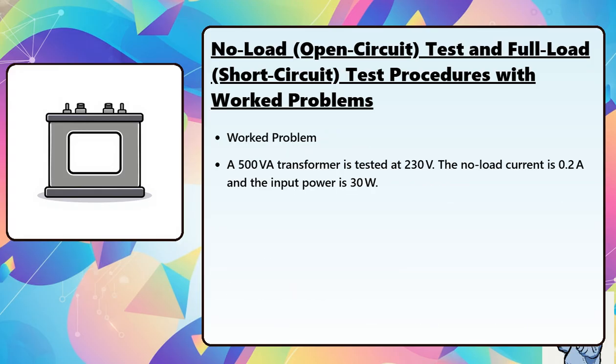Worked problem. A 500 volt ampere transformer is tested at 230 volts. The no-load current is 0.2 amperes, and the input power is 30 watts. R sub C equals 230 squared divided by 30, approximately 1763 ohms. Z sub OC equals V sub OC divided by I sub OC equals 230 divided by 0.2 equals 1150 ohms.